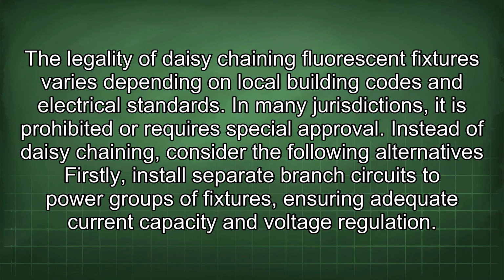The legality of daisy chaining fluorescent fixtures varies depending on local building codes and electrical standards. In many jurisdictions, it is prohibited or requires special approval. Instead of daisy chaining, consider the following alternatives. Firstly, install separate branch circuits to power groups of fixtures, ensuring adequate current capacity and voltage regulation.